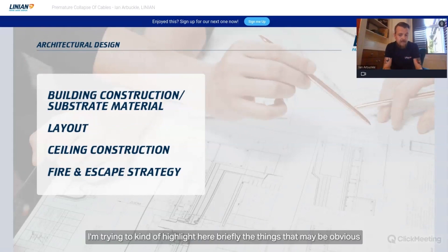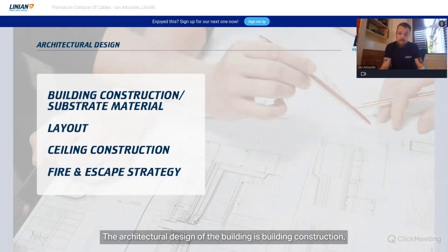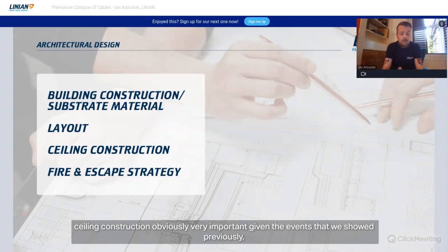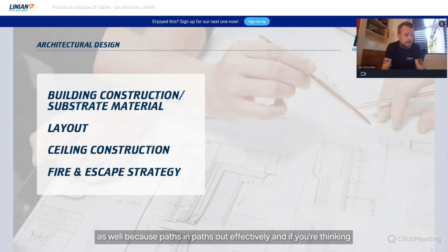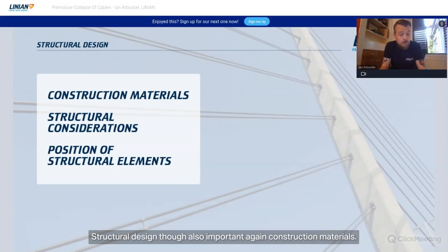In terms of considerations and risk assessment for premature collapse, some things may be obvious to some but not others. The architectural design of the building — construction, substrate materials, architectural layout — is very important because that gets you into the fire engineering aspect. Ceiling construction is obviously very important given the events we discussed. The fire and escape strategy is also critical, because 'paths in, paths out' — the critical path within the building — is ultimately what we're trying to protect.